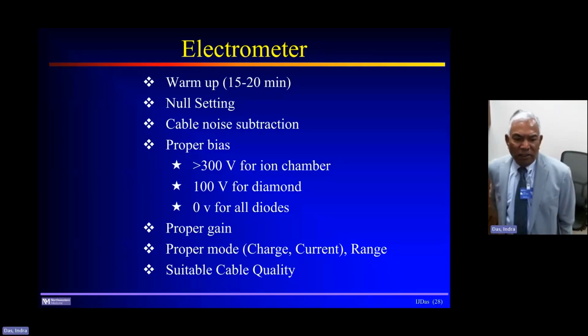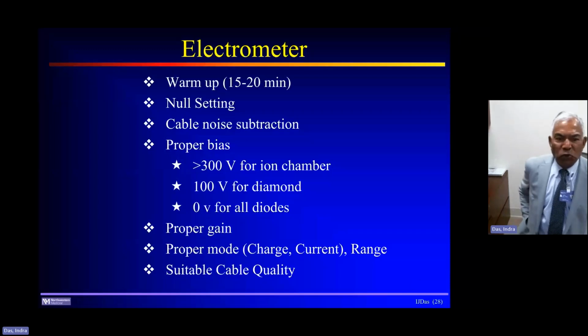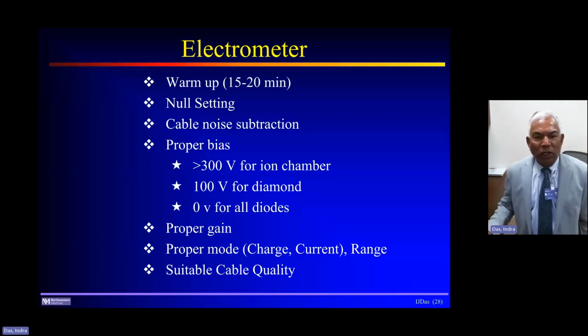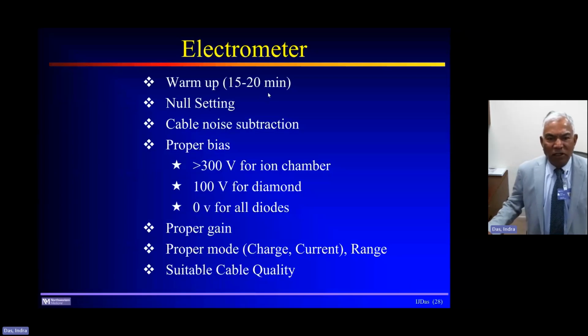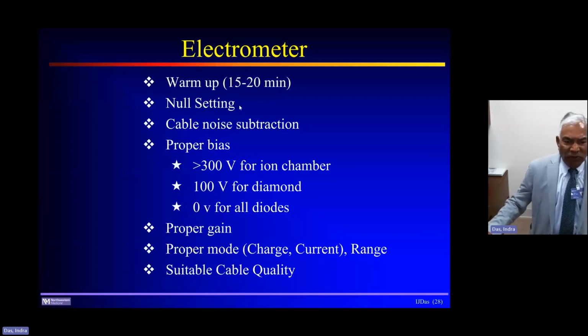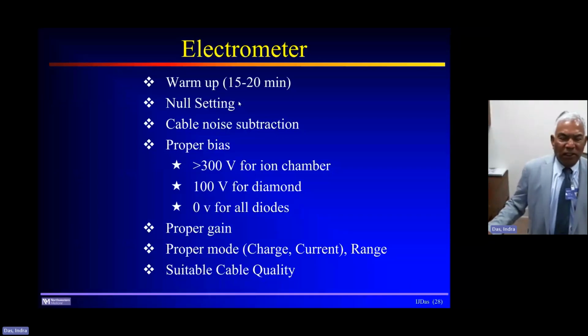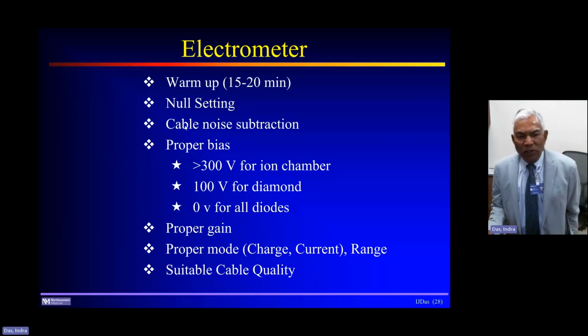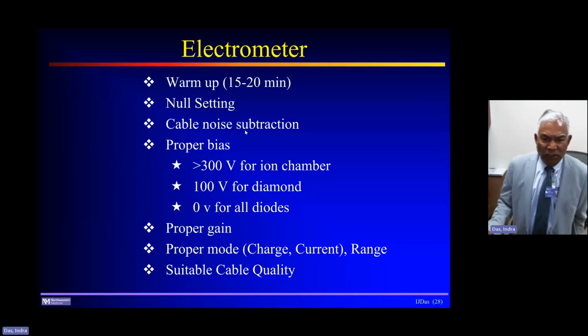Electrometers. That's another caveat that people don't pay attention to, the warm up. You must warm up electrometers, electronics things, and so also the null setting. Even if we are in a rush, you should set the null setting. Every electrometer has the null setting. Also, every electrometer has cable noise subtraction. So please do that too.